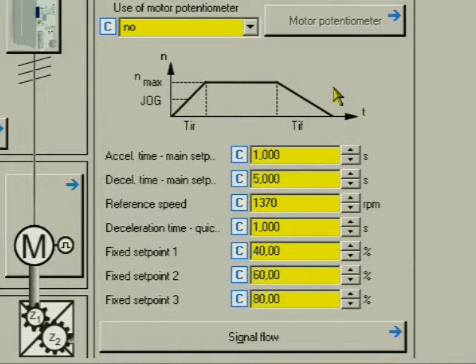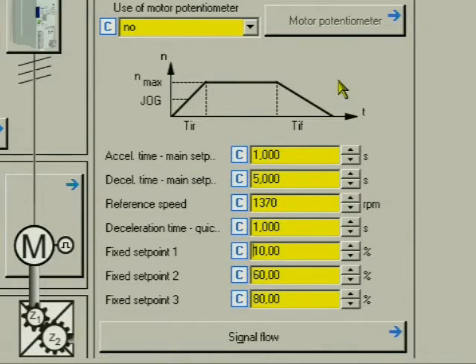For the fixed speeds, we set the setpoints. Fixed setpoint 1 to 10%, this corresponds to creep speed. Fixed setpoint 2 to 50%, this corresponds to half the maximum speed.